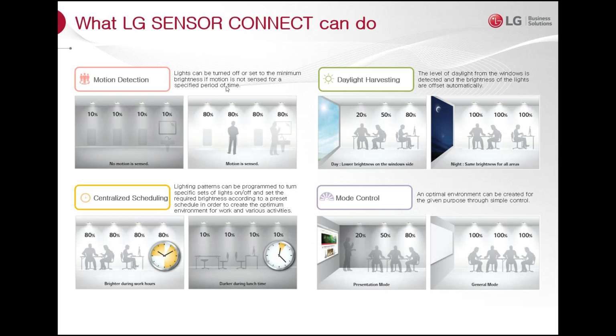If you have a sensor in a group, you can enable daylight harvesting. In daylight harvesting, if you have all sensors in a single location, every sensor will dim individually based on daylight sensing. If you have a combination of sensors and dongles, that's what we call master-slave, in which case all the lights follow the single master and dim together. So you get more granular dimming when you have all sensors.